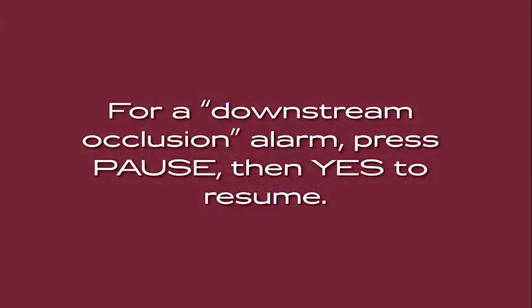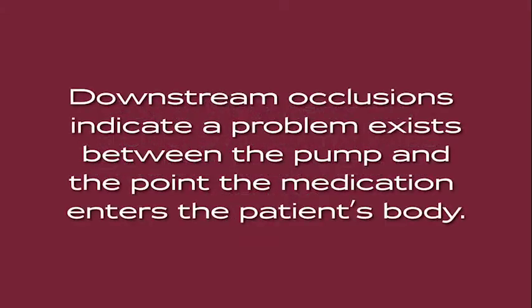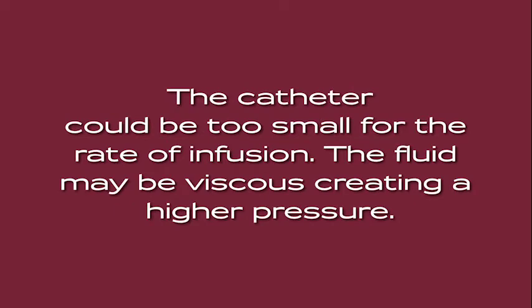For a downstream occlusion alarm, press pause, then yes to resume. Downstream occlusions indicate a problem exists between the pump and the point the medication enters the patient's body. The catheter could be too small for the rate of infusion. The fluid may be viscous, creating a higher pressure.